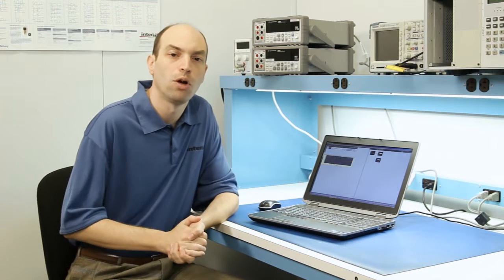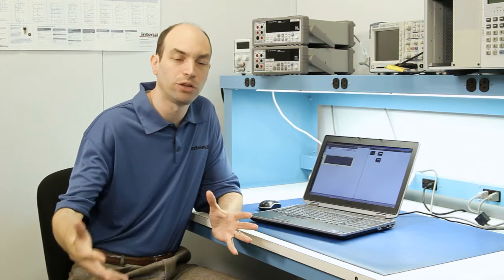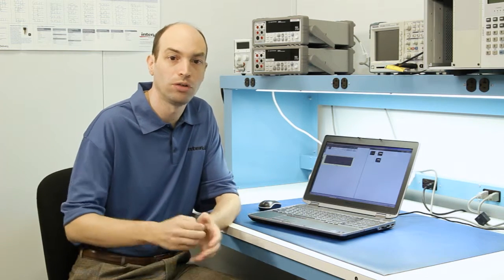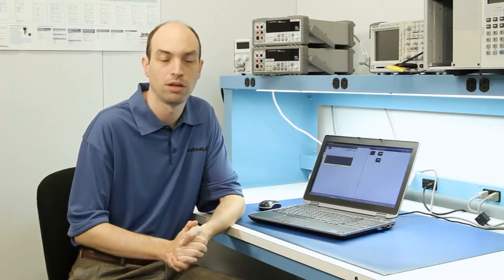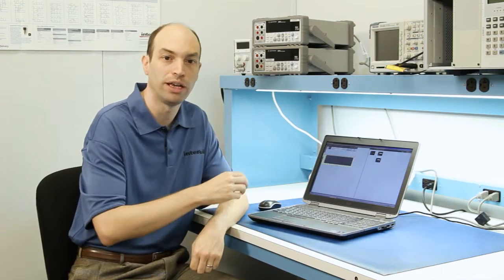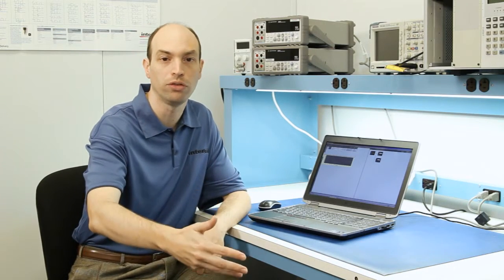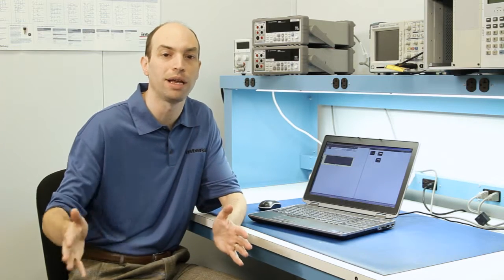The T-on delay, what that means is the amount of delay that you get from the enable signal to when the device starts ramping. So if you have multiple devices and you have one enable going through the entire system, you can then set up a time-based sequencing standpoint. So let's walk through the sequencing box and let's look at all the other options above the graphical readout.